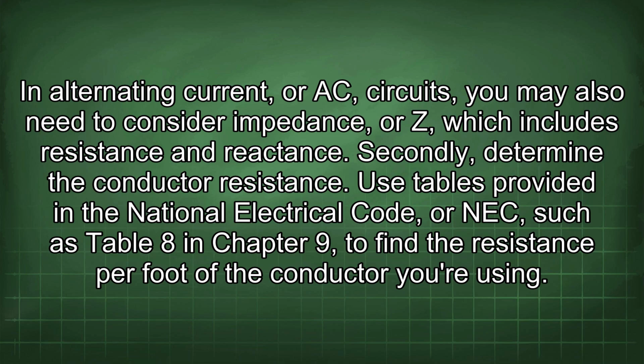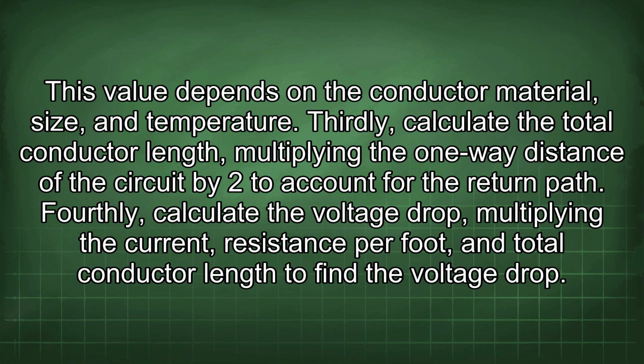Secondly, determine the conductor resistance. Use tables provided in the National Electrical Code, or NEC, such as Table 8 in Chapter 9, to find the resistance per foot of the conductor you're using. This value depends on the conductor material, size, and temperature.